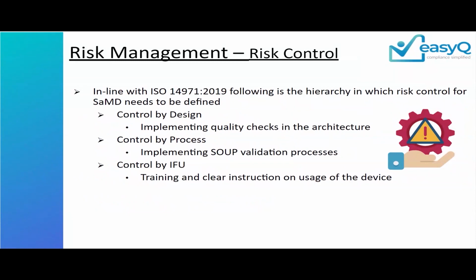And this again, I speak from my practical experience rather than looking into any standard. Making a risk zero basically means that the feature is no more available, right? As long as that feature is there, there will always be a remote chance of that feature not working or creating some sort of risk. Your probability of occurrence or your severity of harm might go low, but turning it into zero means that that particular feature itself doesn't exist, right?